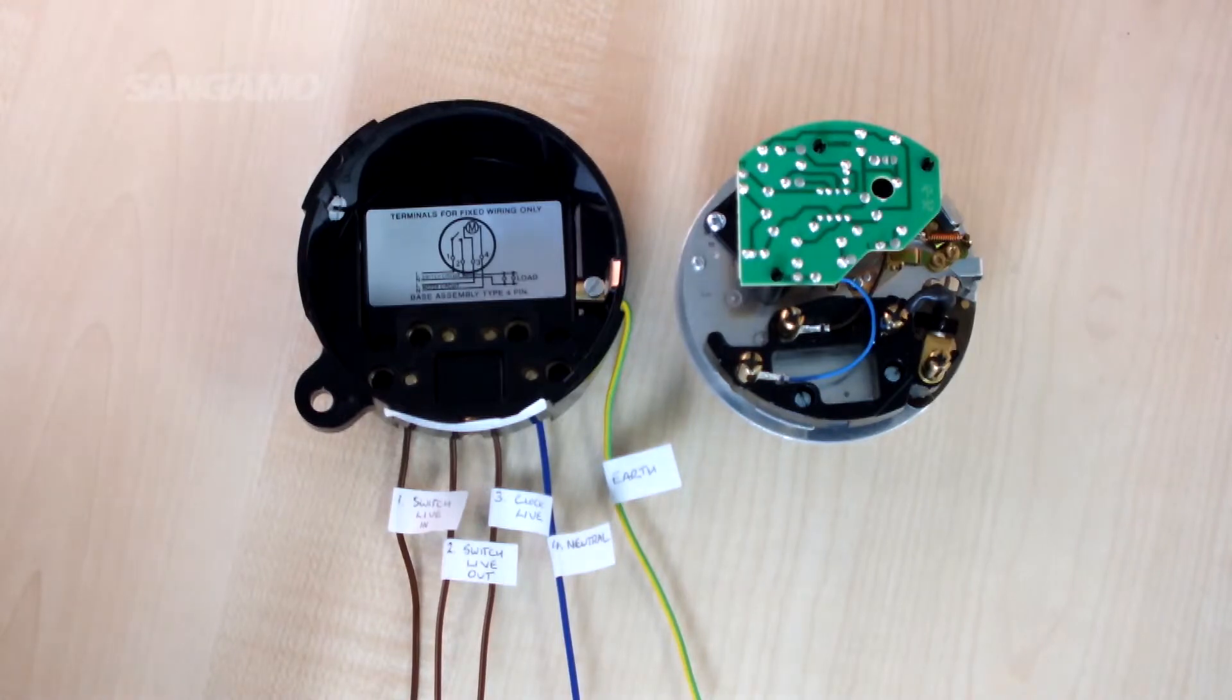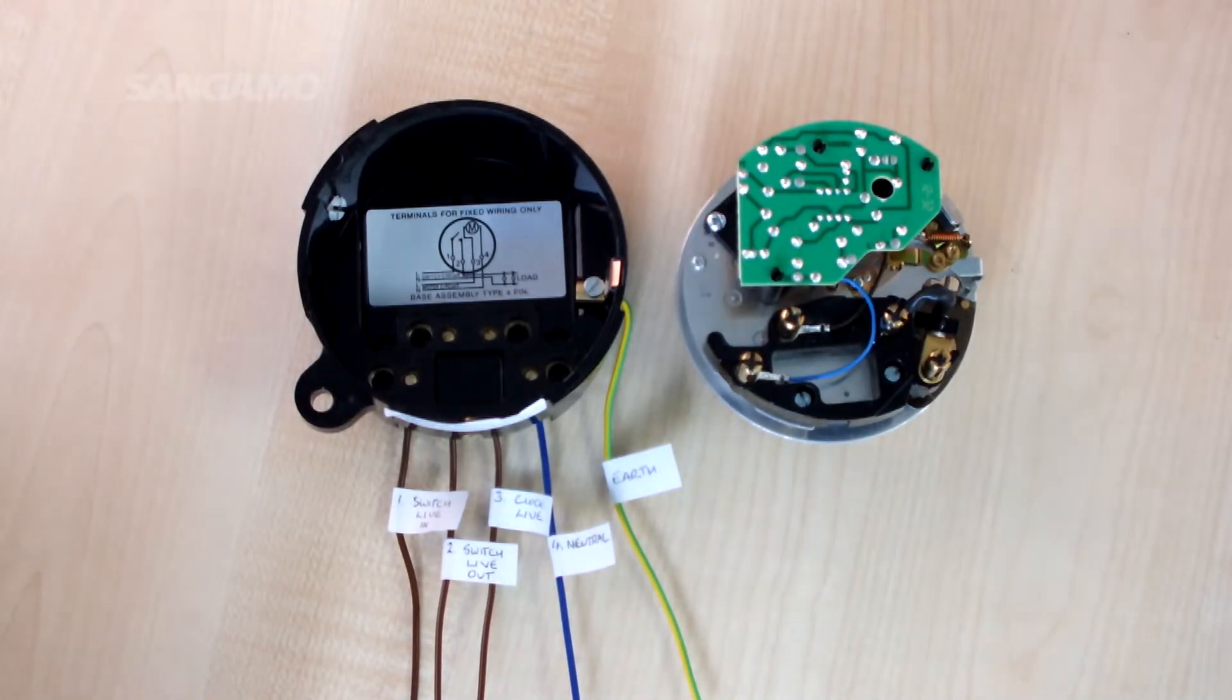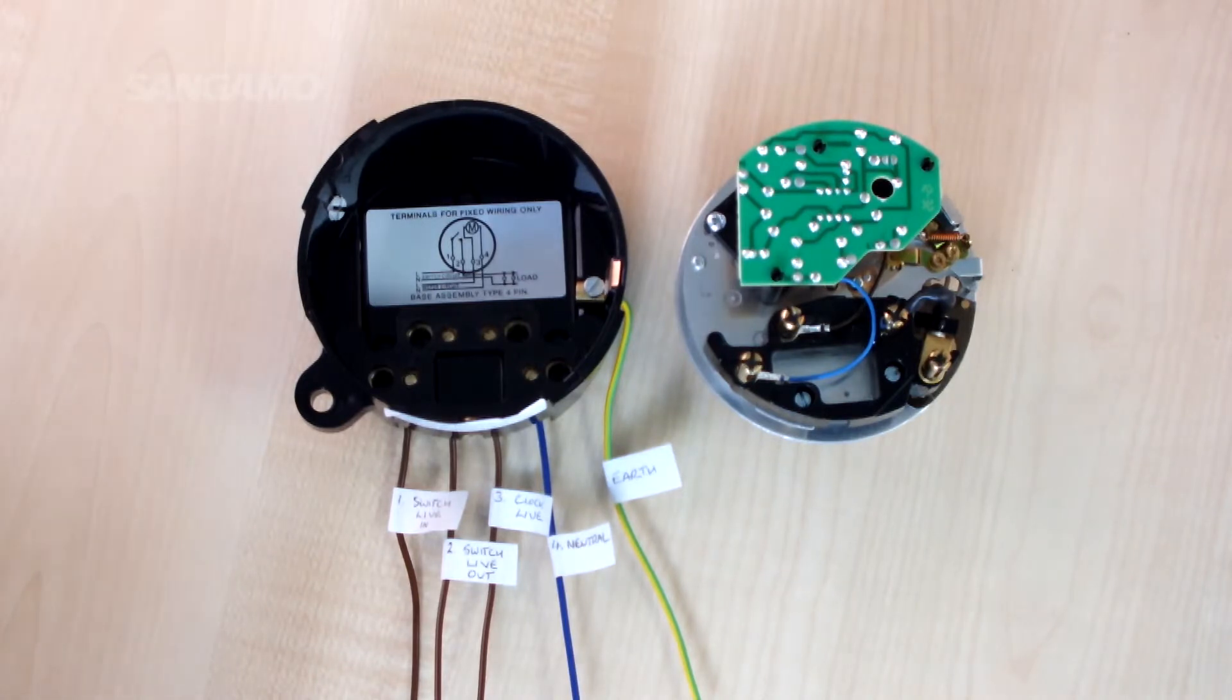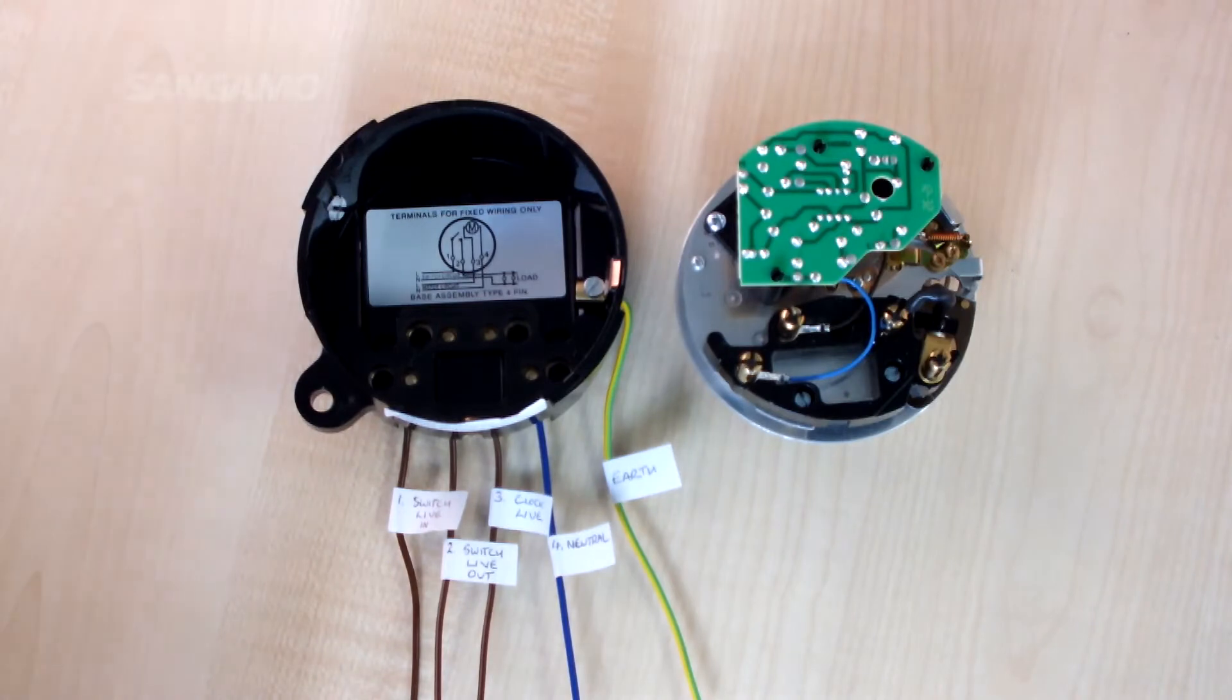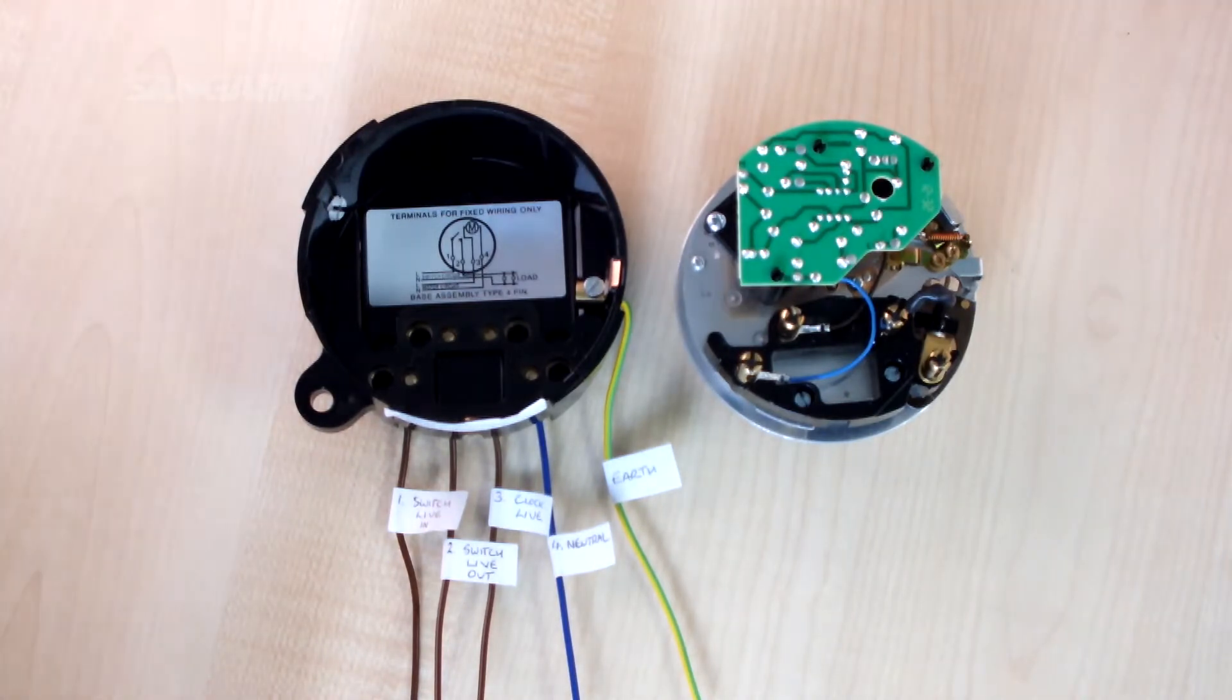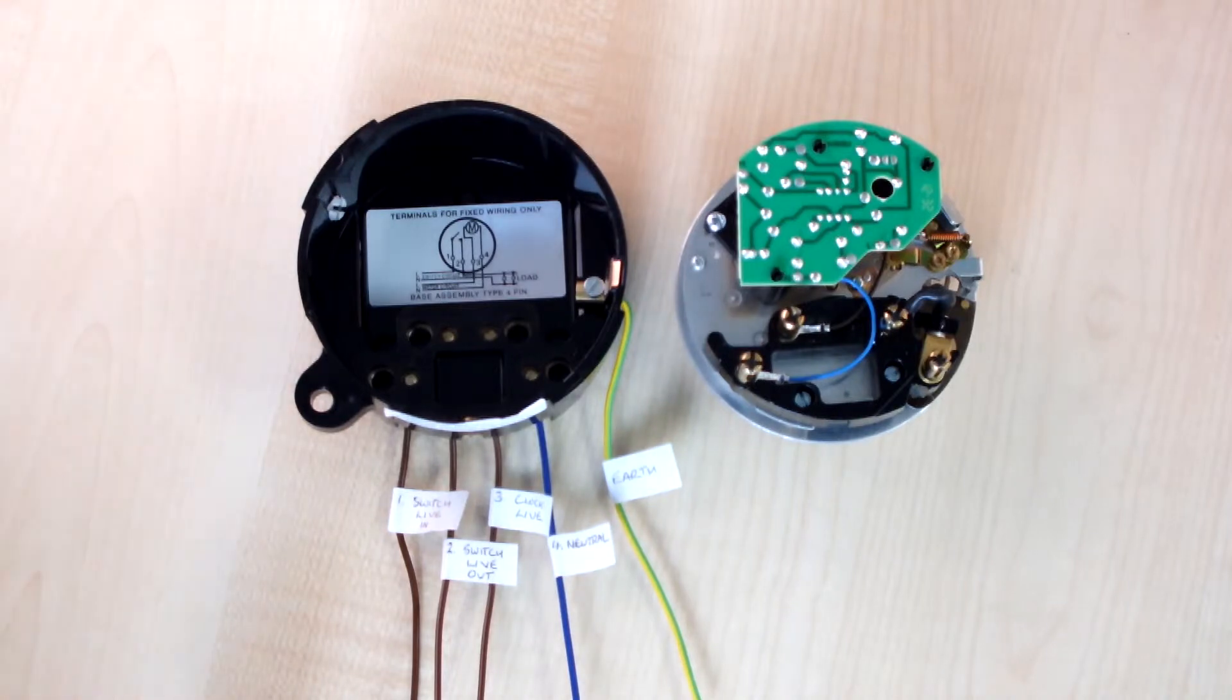If we look at 4 pin time switches now, these have independent clock and switch connections which enable a different AC switching circuit voltage to be controlled from that of the 230 volts required to run the clock. For instance, you may wish to switch a 110 volt AC machine.